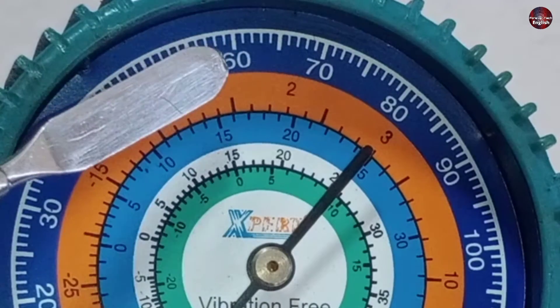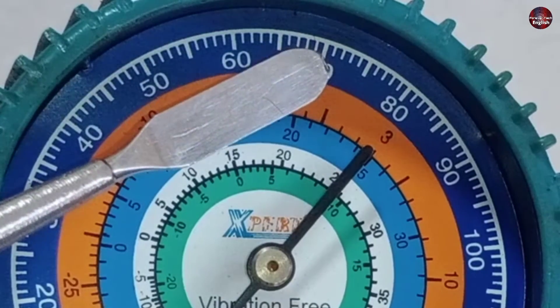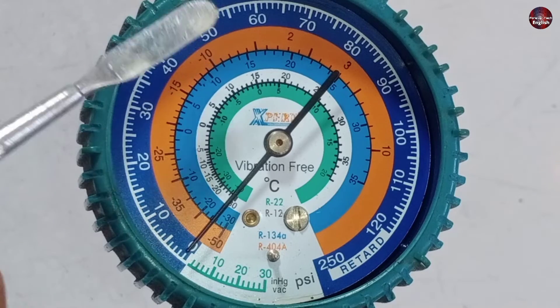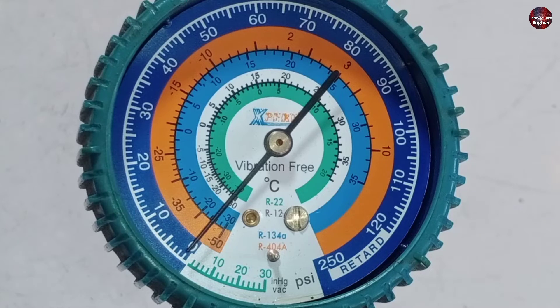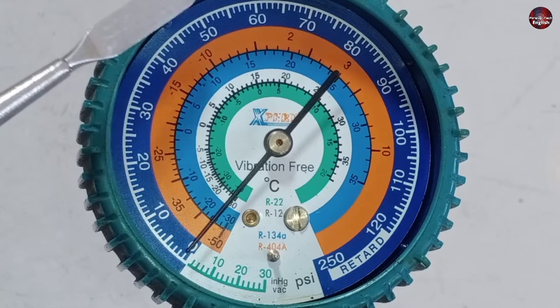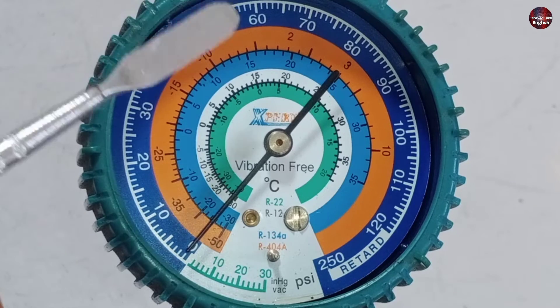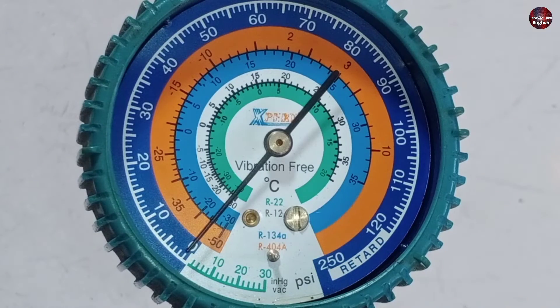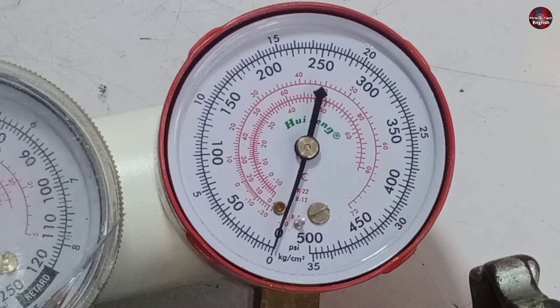Conventional R22 units have a back pressure from 60 to 70 PSI when the refrigerant is converted from a liquid state to vapor. So the saturated temperature of R22 refrigerant should be 2 to 3 degrees Celsius. Different refrigerant temperatures are given on this gauge for their specific pressures.